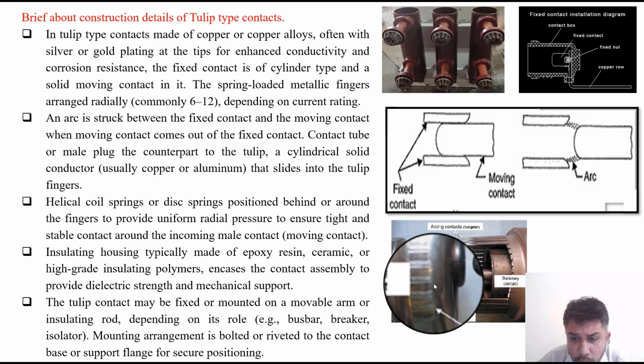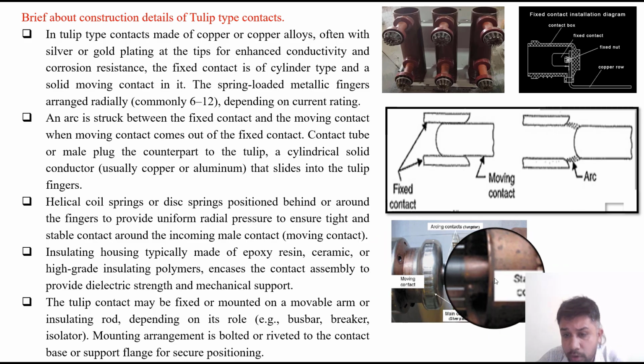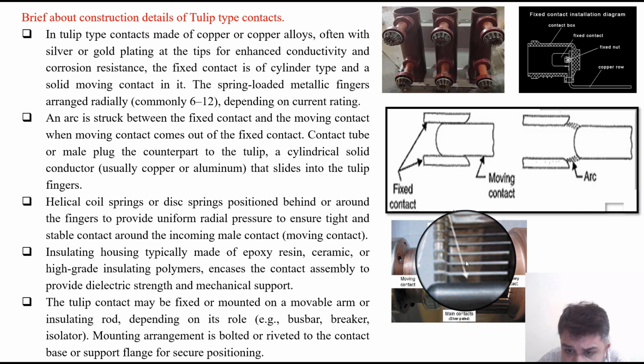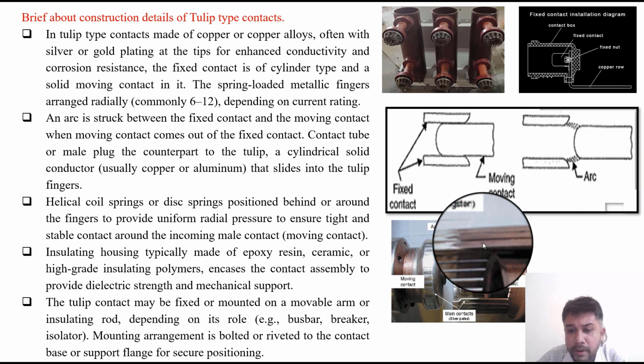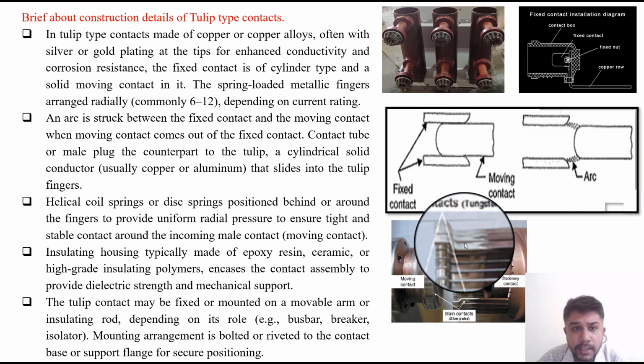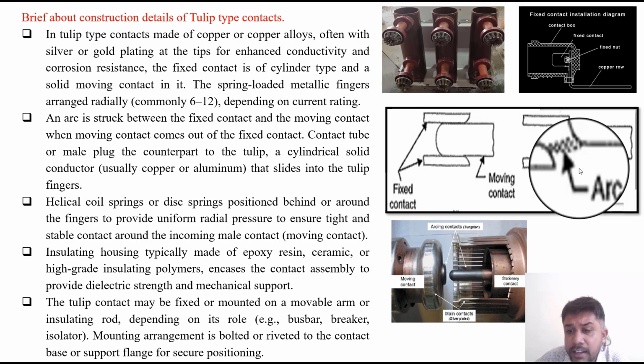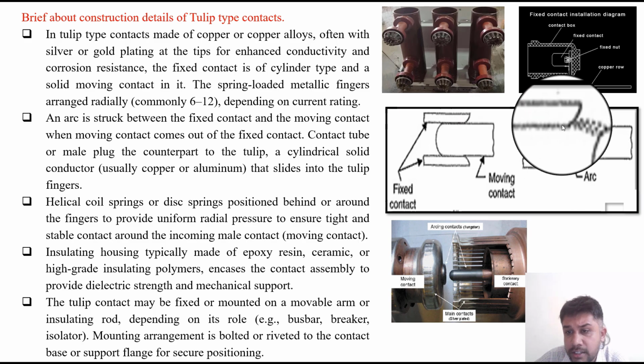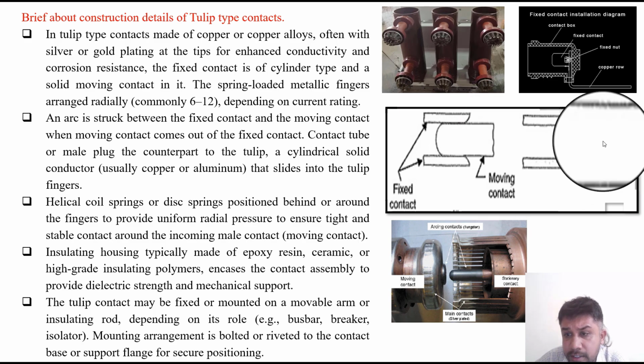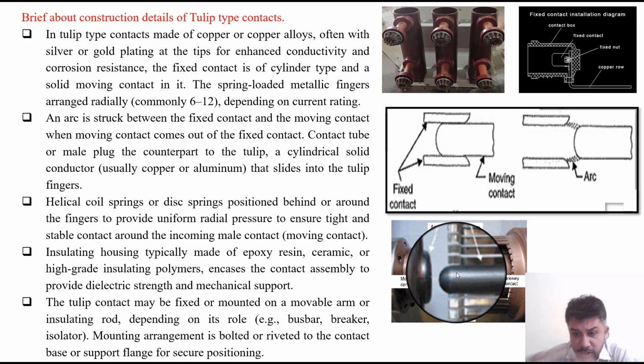This is the moving contact, this is a stationary or fixed contact, and these are the fingers made up of copper or copper alloys. Silver plating is done. The arc is struck between the fixed contact and the moving contact when the moving contact comes out of the fixed contact. So the arc is struck between these two contacts. These are some fixed contacts and this is the moving contact which moves away or out of these fixed contacts.